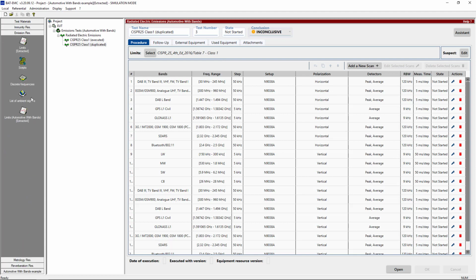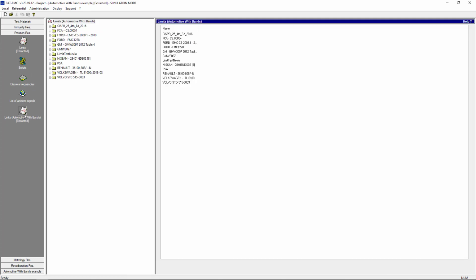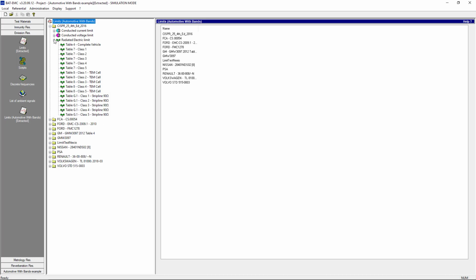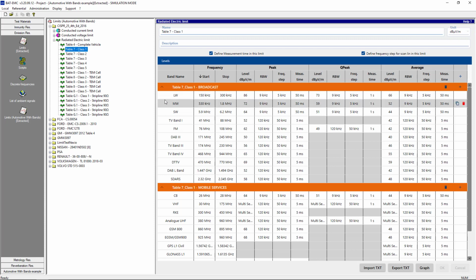If we go to the emission resources, we have a new section called Limits for the Automotive with Bands. Keep in mind that just as before, Nexio personnel create these limits. We provide these limits to you, but we also train how to create your own limits as well as to edit the existing ones. Table 7 Class 1 was the one I mentioned, and you will note that all the bands, like we were looking at before from the standard, are listed sequentially. You can also note that not only are the limits for those emissions for the different detectors captured, but also the settings required. An additional feature is shown above because we have two more boxes, define measurement time and define frequency step. This is not required, but by doing so, it's a time saver because whatever you enter here for those measurement times and the frequency steps will be used as default later, and then when the test configuration window appears, you can of course edit those if you needed to change them later.